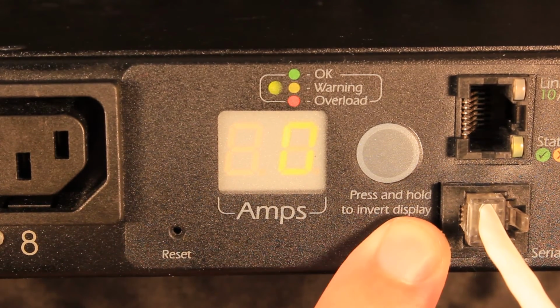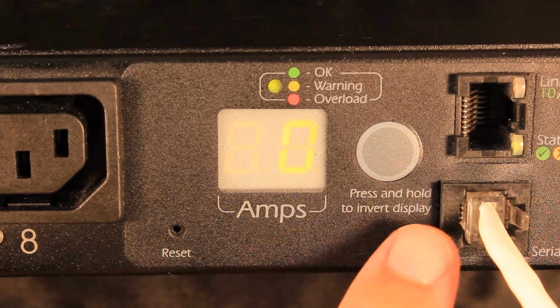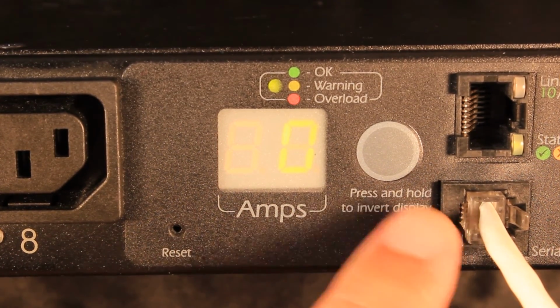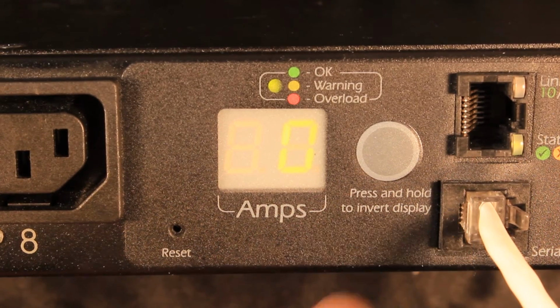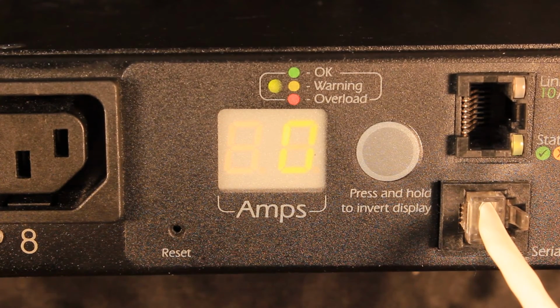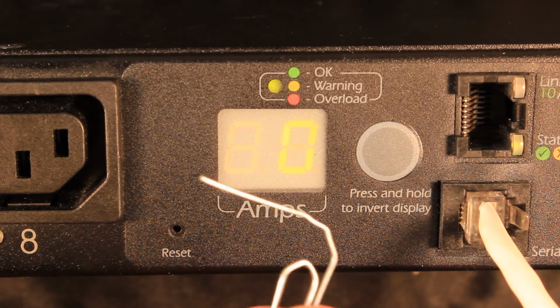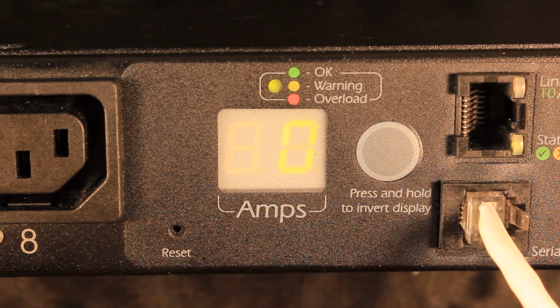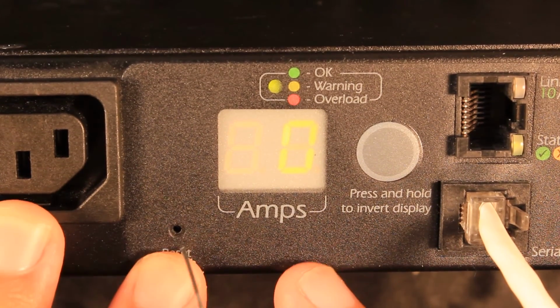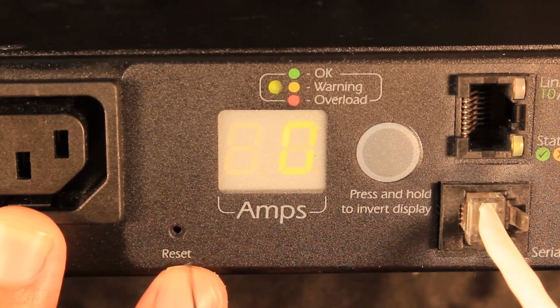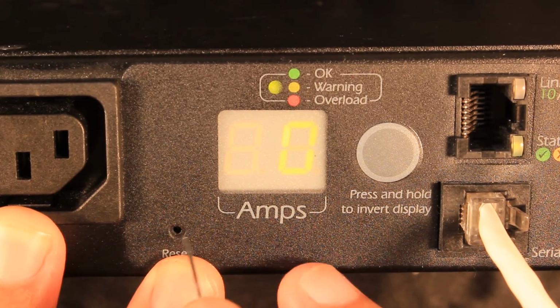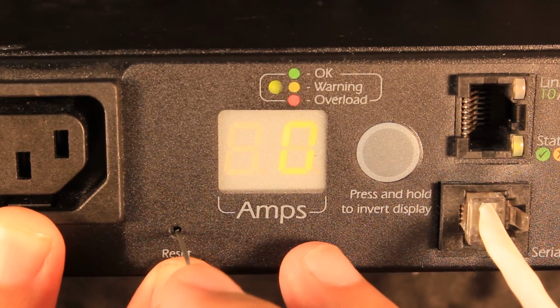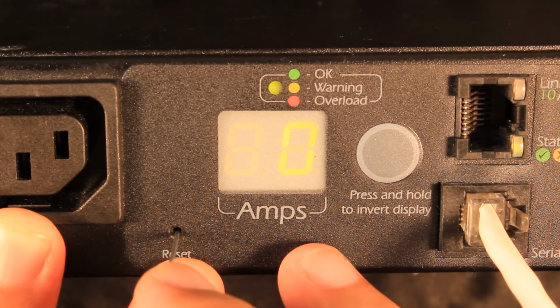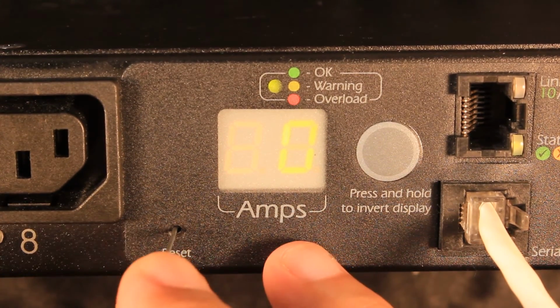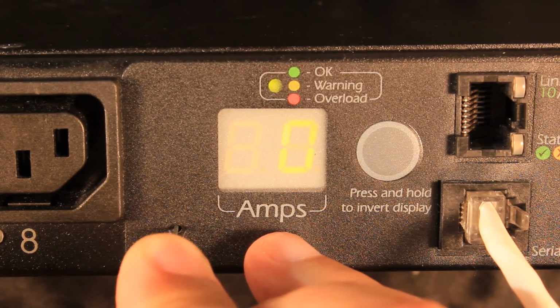After establishing a good working connection to the serial port of the power distribution unit, now is the time to initialize the reset procedure. Take something sharp and push it where it says reset. There's a small tactile button right below. Insert it into the hole, push it down, and keep it pressed for 10 to 12 seconds.